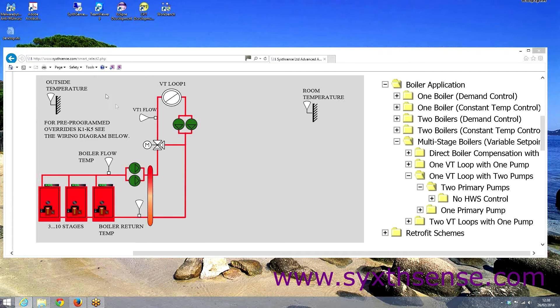What we can see here on screen is an example. This is a boiler plant with three boilers going through to a VT loop where we have twin pumps on a VT circuit. VT means variable temperature, so we have a weather compensated temperature control modulating a 3-point valve, and on the primary circuit side we have twin pumps.